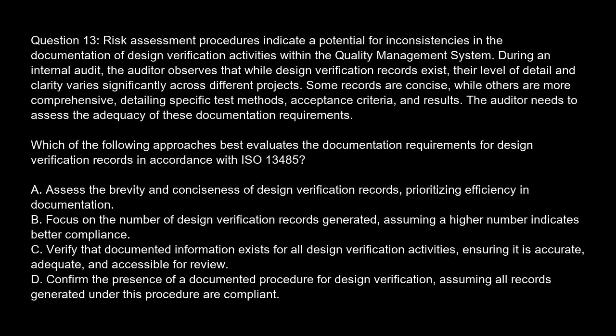Which of the following approaches best evaluates the documentation requirements for design verification records in accordance with ISO 13485? Option A. Assess the brevity and conciseness of design verification records, prioritizing efficiency in documentation. Option B. Focus on the number of design verification records generated, assuming a higher number indicates better compliance. Option C. Verify that documented information exists for all design verification activities, ensuring it is accurate, adequate, and accessible for review. Option D. Confirm the presence of a documented procedure for design verification, assuming all records generated under this procedure are compliant.